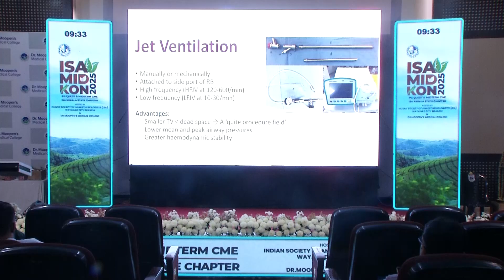The other thing to keep in mind with jet ventilation is that your driving pressure and I:E ratio should be adjusted. The pressure should be maintained around 20 psig, and inspiration should be limited to 30 to 40% of the respiratory cycle. The most important point is to always make sure that the outflow, the expiratory gas flow, is not obstructed, otherwise it can cause barotrauma. That is the most important complication with jet ventilation, barotrauma causing pneumothorax, pneumomediastinum or subcutaneous emphysema.